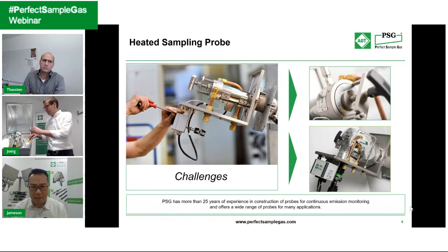You making sure that your acid dew point is handled, is hot enough without a cold spot. You make sure that the process is maybe 500 degrees. How can my sample probe, which is 180 degrees, be able to adapt to the 500 degree process?